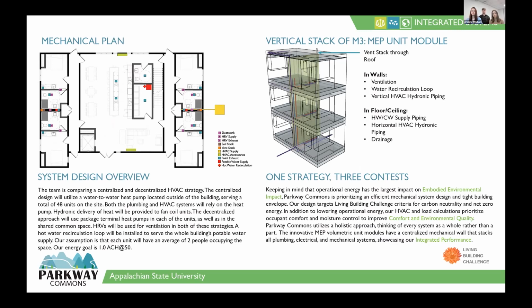This will entail having a large air-to-water or water-to-water heat pump that creates hot or chilled water sent to the dwellings via a variable primary flow pump system. Fan-coil units are installed in each dwelling unit to serve occupants' heating and cooling needs. Domestic hot water may also be produced through this system. We'll leverage the central shared wall and mechanical modules to distribute water and ventilation air from the heat recovery ventilator, along with the soil and vent stacks connected to each unit. The central mechanical corridor innovation is the heart of this design strategy.